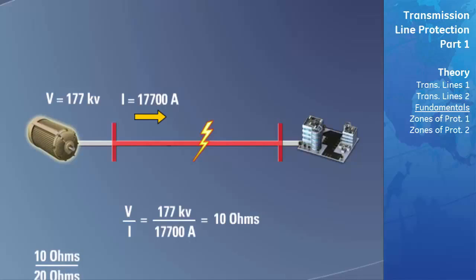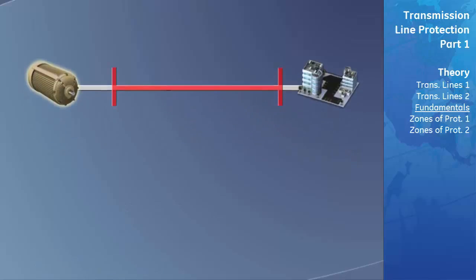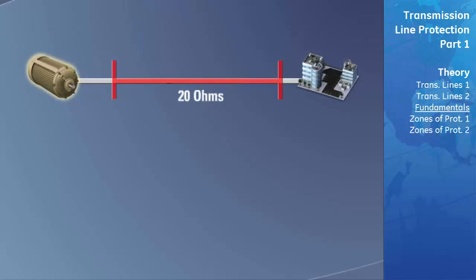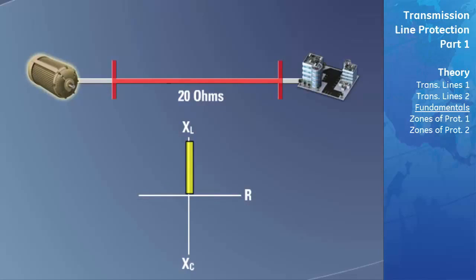In this example, the current increased as a result of the reduction in impedance from 20 to 10 ohms, indicating that the fault occurred at a distance of 50% from the measurement point to the end of the transmission line. The impedance of the line is often drawn on an RX diagram. The x-axis represents the resistive component of the impedance. The y-axis represents the inductive component in the positive direction, and the capacitive component in the negative direction.